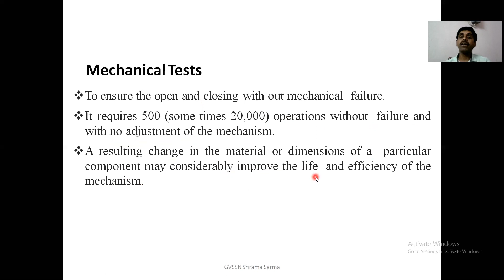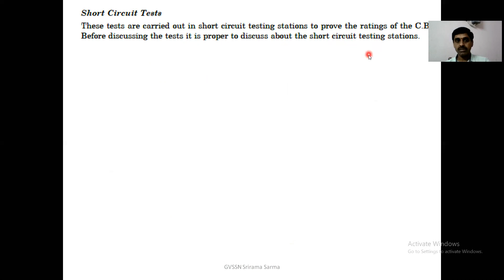Coming to the short circuit tests, these tests are carried out in short circuit testing stations to prove the ratings of the circuit breakers. Before discussing these tests, it is proper to discuss the short circuit testing stations, the different types of stations. There are two types of testing stations: field type and laboratory type. In the field type, the power required for testing is directly taken from a large power system, so the breaker to be tested is connected to the system directly.